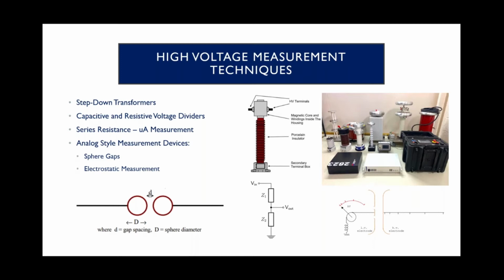You also have electrostatic measurements, which you can see in the picture down in the bottom right. Similar concept, but what it's going to be doing is the two poles will never get close enough to flash over, but instead it will use the fields generated by the high voltage side and pull a mechanical indicator, which is physically moved to indicate the level of the field that is being generated from that high voltage on the other electrode.